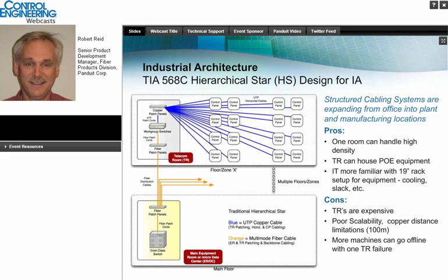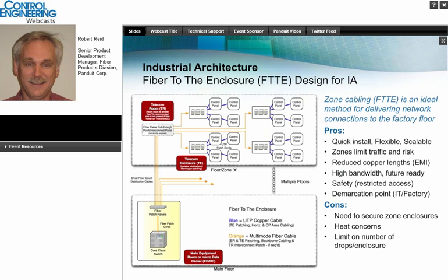In terms of an industrial application, this is probably not the greatest solution because TRs consume brick and mortar. They can be very big, and one of the things you might want to consider is breaking up that TR into multiple TEs, which I'm showing here. So that gives you a lot more flexibility. So a TE is a telecom enclosure.